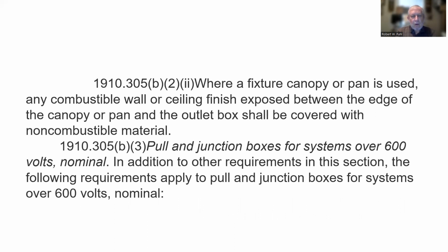Combustible wall or ceiling finish. That's something that's frequently overlooked in construction. They think their building is not going to burn. The building itself is made of non-combustible materials, but then inside it, they put finishes and furniture and everything else that is combustible, and they wonder why it burnt down anyhow.